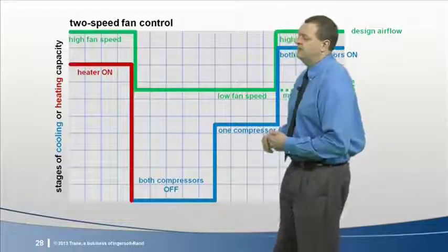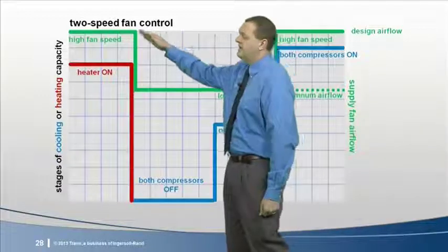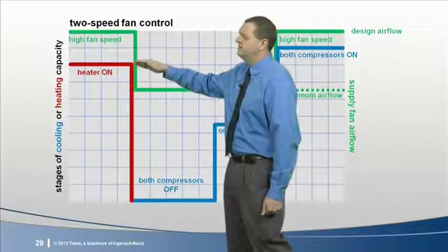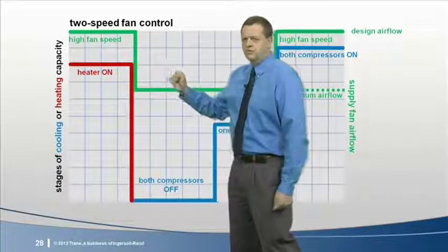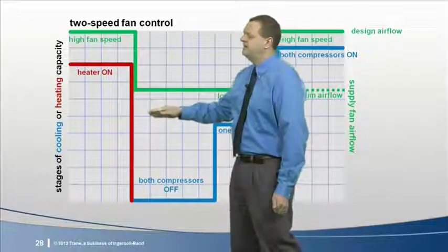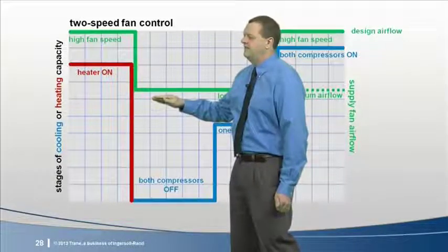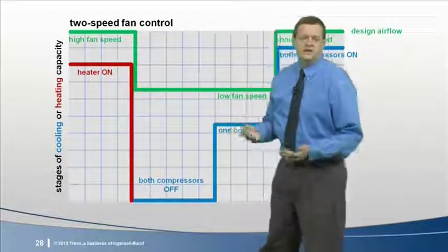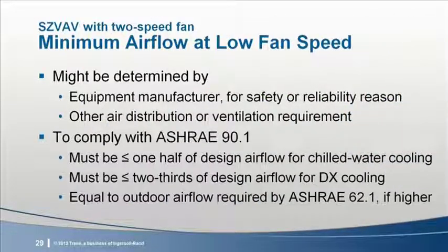Finally, if the thermostat calls for heat, the fan operates at high speed and the heater turns on. When the zone warms up, the thermostat shuts off the heater and the fan returns to operate at this low speed. Now, like with variable speed fan control, the minimum airflow at the low fan speed might be determined by equipment design for safety or reliability reasons. And again, Standard 90.1 requires this minimum airflow to be no higher than 2/3 of design airflow for DX equipment, or 1/2 of design airflow if it's chilled water.